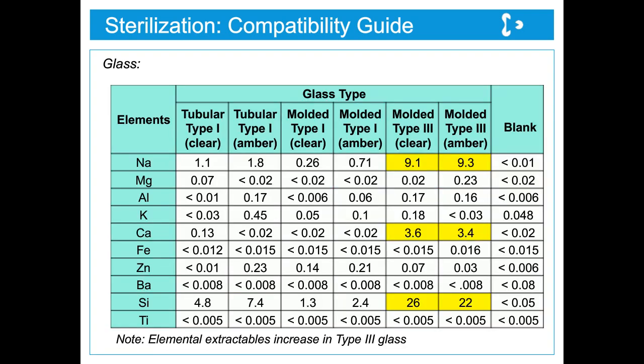In this experiment here, I wanted to really show you how steam sterilization can affect type 3 glass. I have in this table the elements that can come out of glass. These are inorganic elements that can come out of glass. On the left-hand side, you can see it's sodium, magnesium, aluminum, potassium, calcium, iron, zinc, barium, silicon, and titanium.